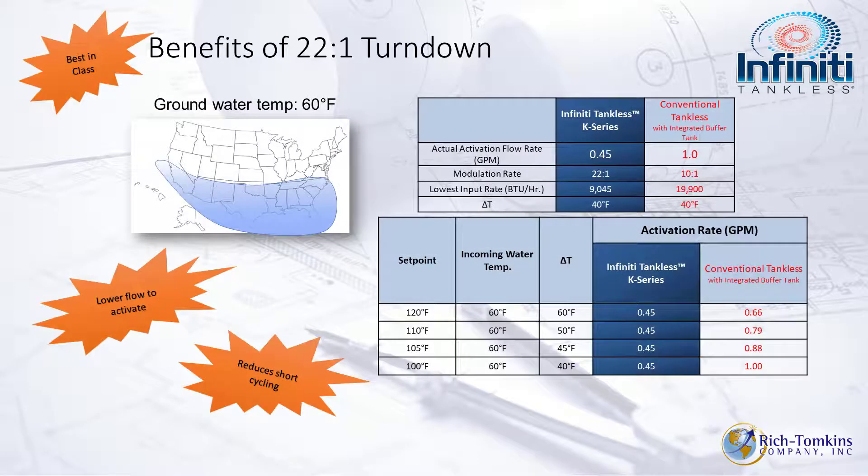Circling back to the benefits of that 22 to 1 turndown ratio: in southern climates, this unit activates at just 0.45 GPM. Comparing it to a conventional tankless across Delta T's from 40 to 60 degrees, conventional units have activation flow rates ranging from 1.0 GPM down to 0.66 GPM, while the Infiniti K stays at 0.45 GPM right across all those Delta T's.